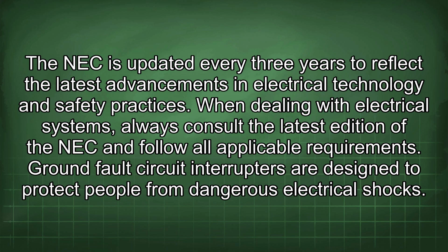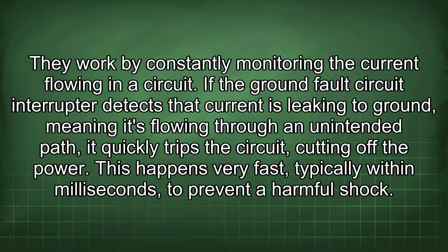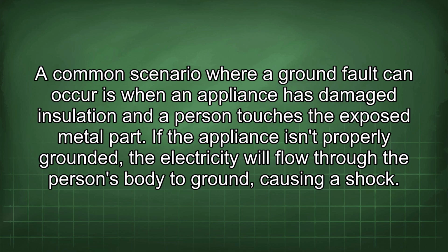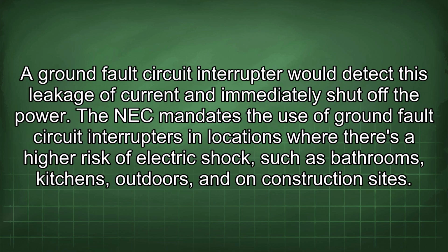Ground fault circuit interrupters are designed to protect people from dangerous electrical shocks. They work by constantly monitoring the current flowing in a circuit. If the ground fault circuit interrupter detects that current is leaking to ground, meaning it's flowing through an unintended path, it quickly trips the circuit, cutting off the power. This happens very fast, typically within milliseconds, to prevent a harmful shock. A common scenario where a ground fault can occur is when an appliance has damaged insulation and a person touches the exposed metal part. If the appliance isn't properly grounded, the electricity will flow through the person's body to ground, causing a shock. A ground fault circuit interrupter would detect this leakage of current and immediately shut off the power.